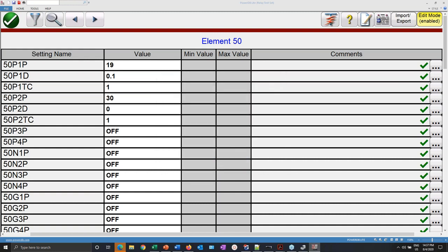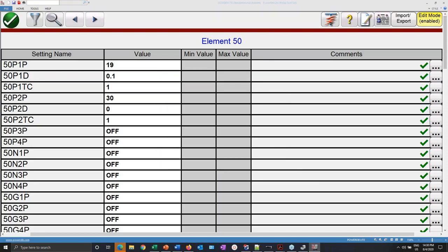Okay, you can reuse it. You can change the names and whatnot. You can test the same relay several times. Let's say you have to test the same relay every 2-3 years. You can reuse the same test sheet to test the same relay. Once you create this automation, you can apply it to as many relays as you want. Typically, the settings that matter don't change the name over time. So you can use it over the different generations of the same type of relay.